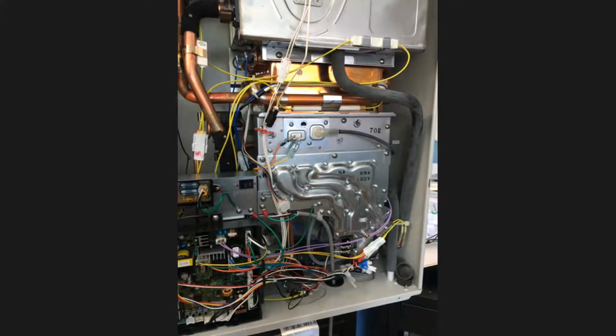Ray's asking whether these provide domestic hot water and space heating. Ray, these are a specific domestic hot water model. One allowed use, especially here in the Commonwealth of Massachusetts, is tying this into an air handler, using the potable water to heat an air handler and provide domestic hot water for the space. It does mix them, but it's done frequently—there are thousands of tank type water heaters installed this way throughout the Commonwealth. This is an option for a replacement.